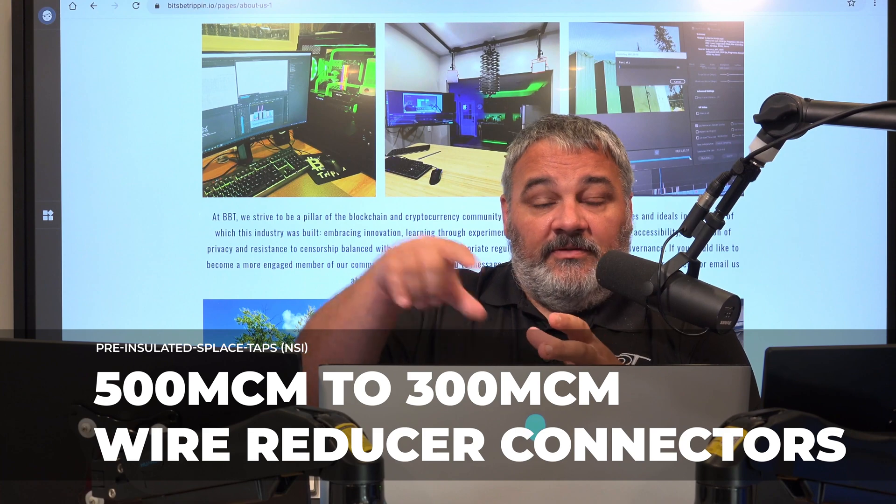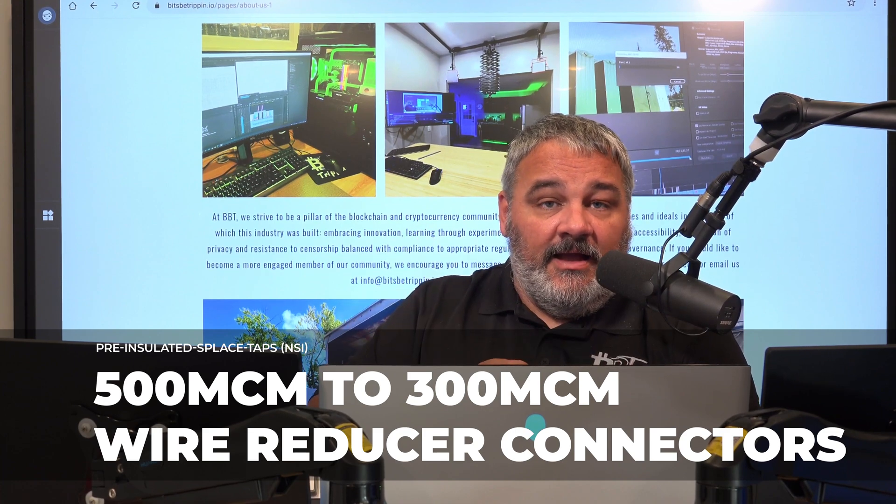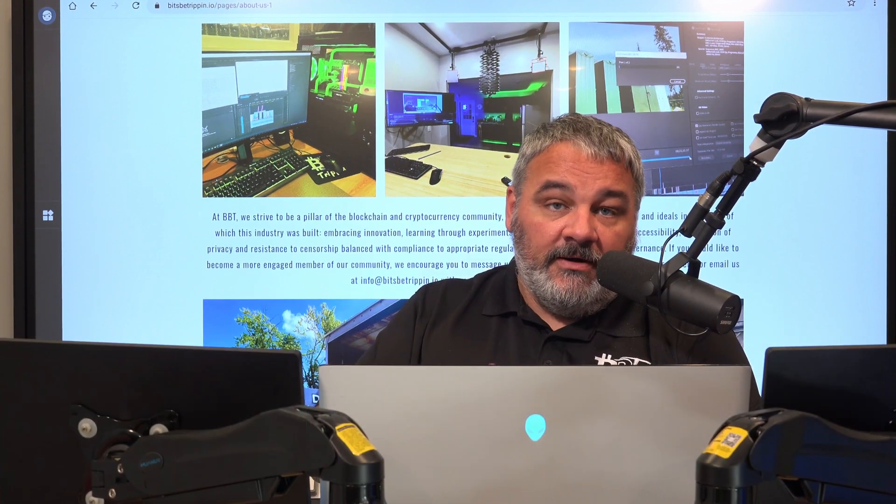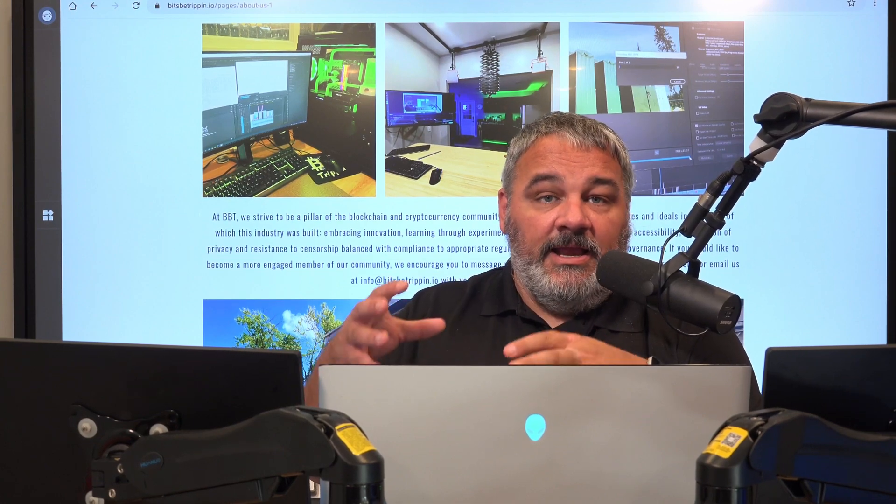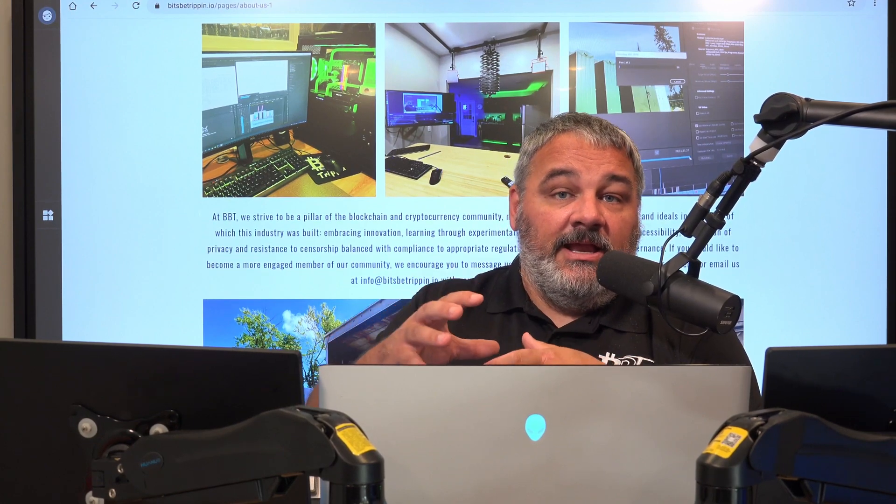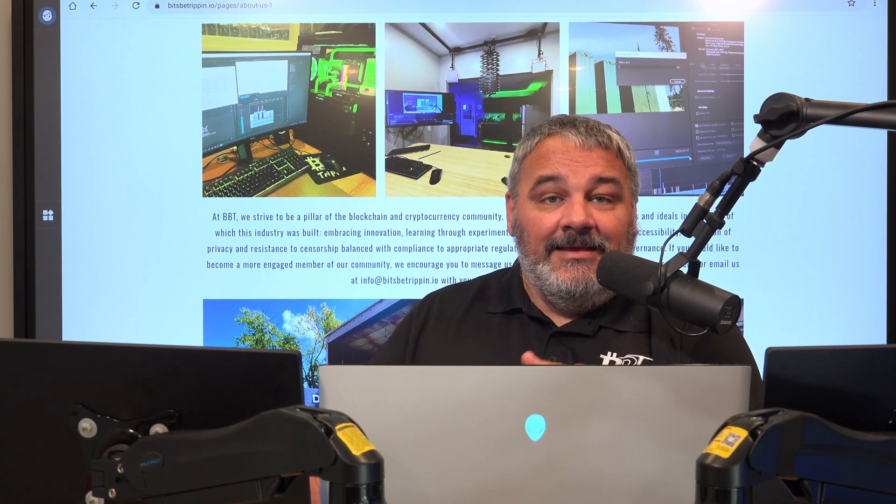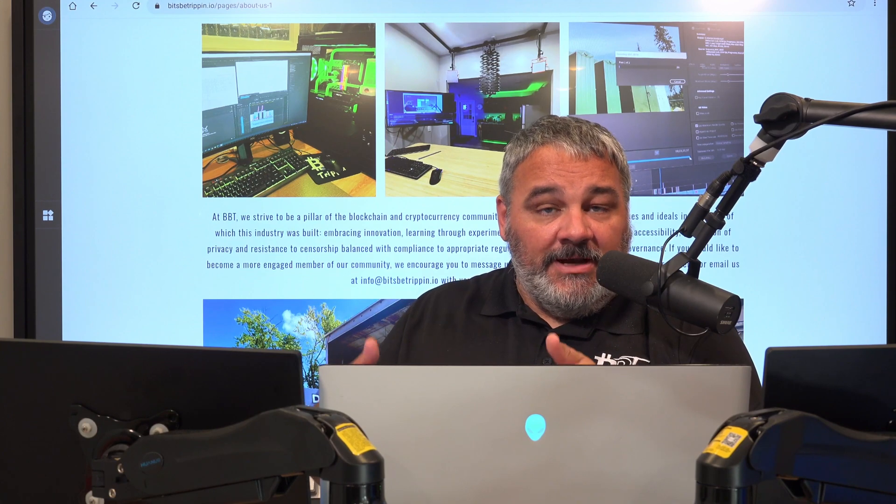Looking to make sure like the NSIs, the things from our transformer to our panels, we use these step down NSIs. Those need to be re-torqued just to make sure that over time the containers are vibrating and is there any kind of looseness that happens with the connections. We check heat on the lines themselves, check the transformer, make sure it's looking good.